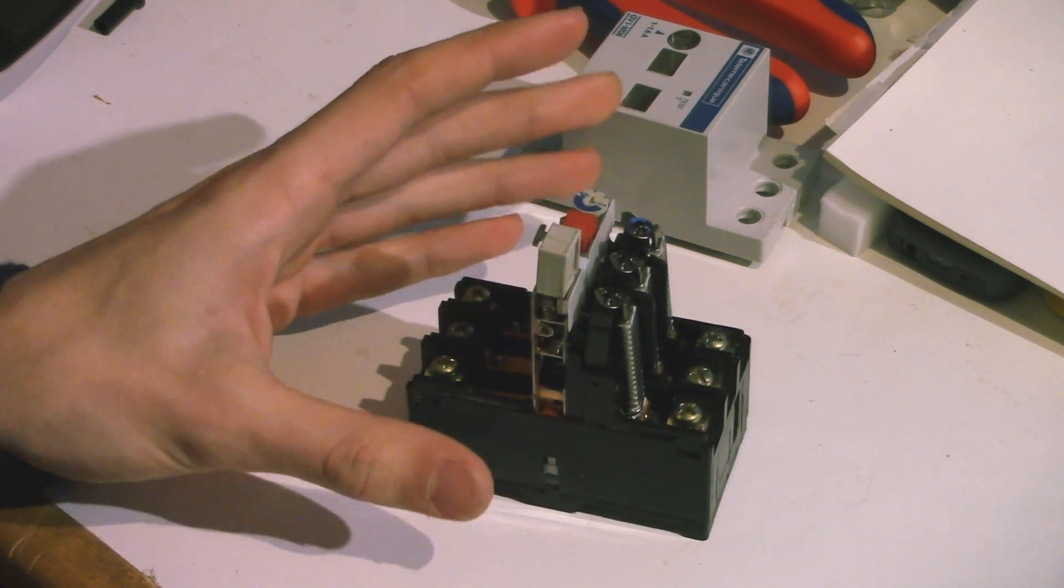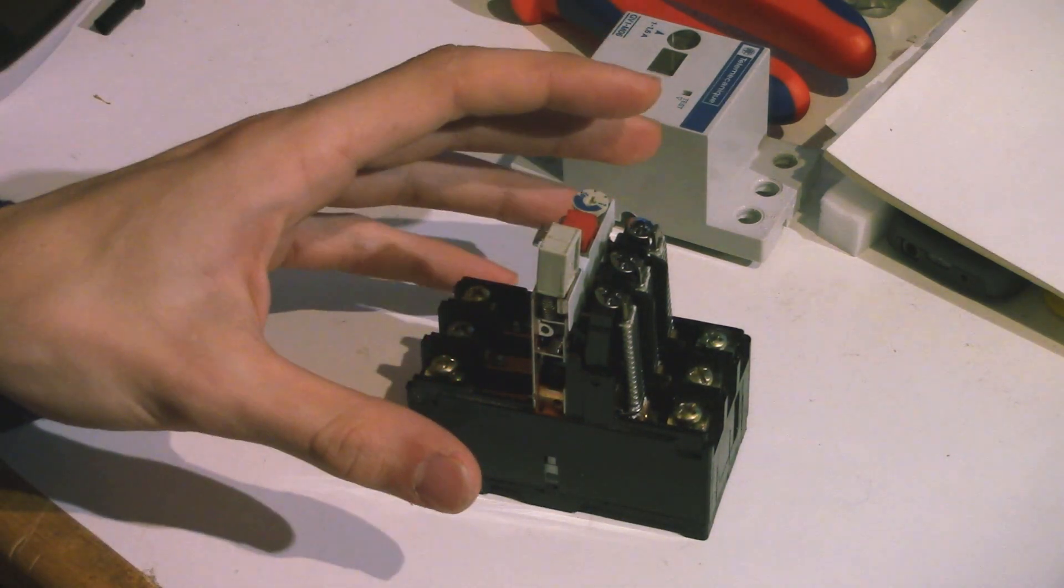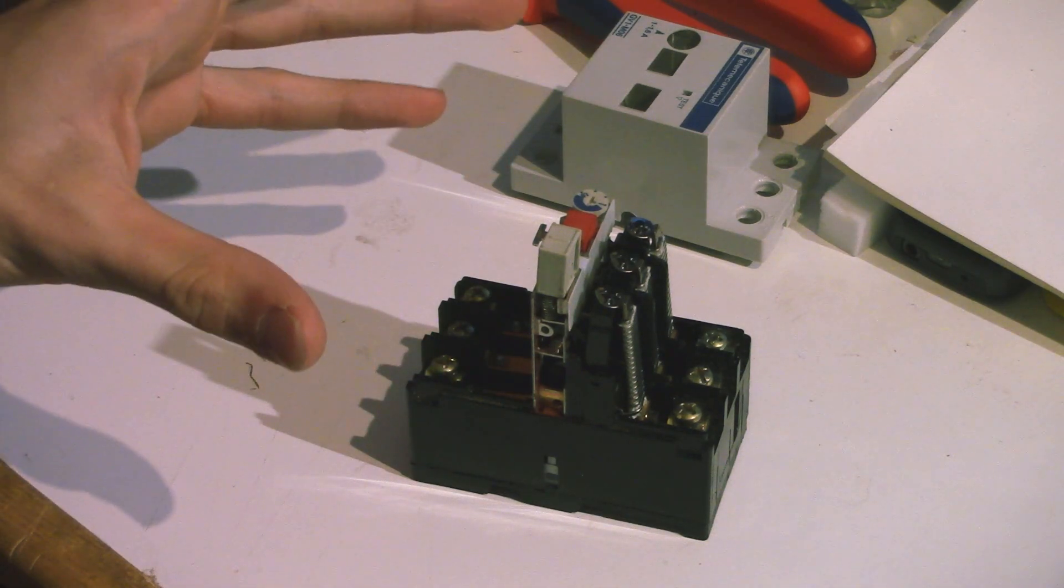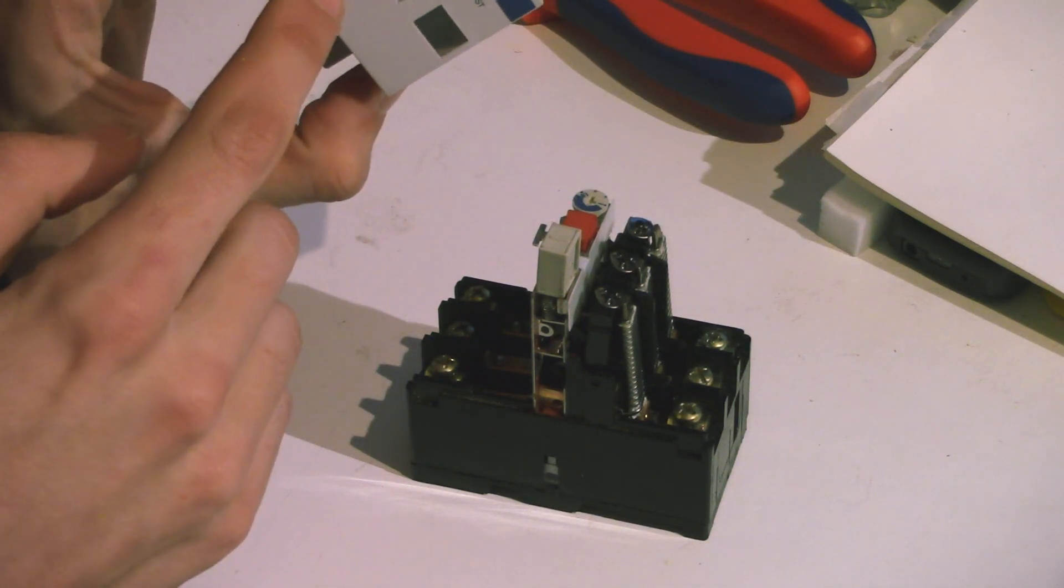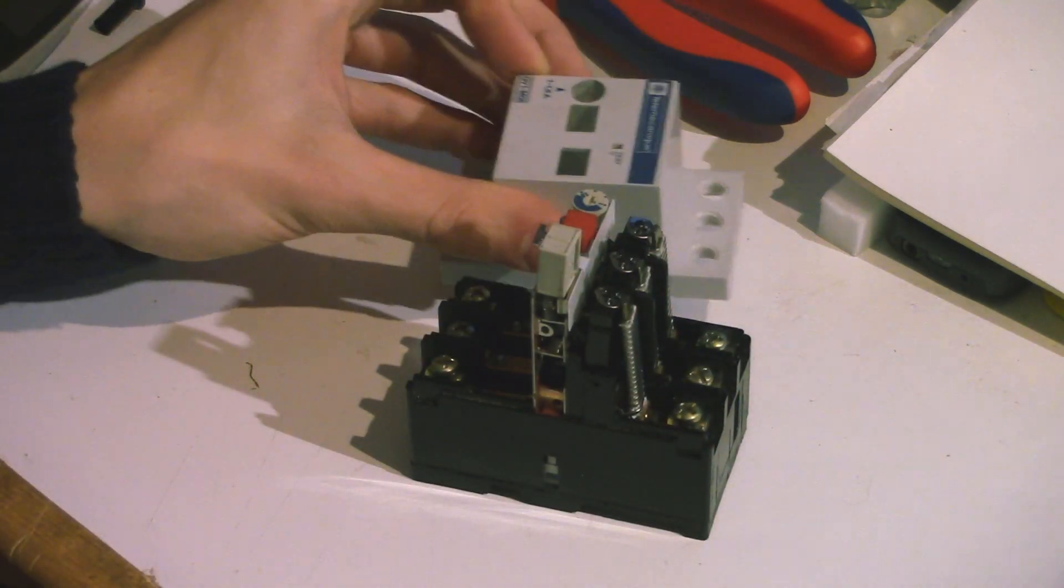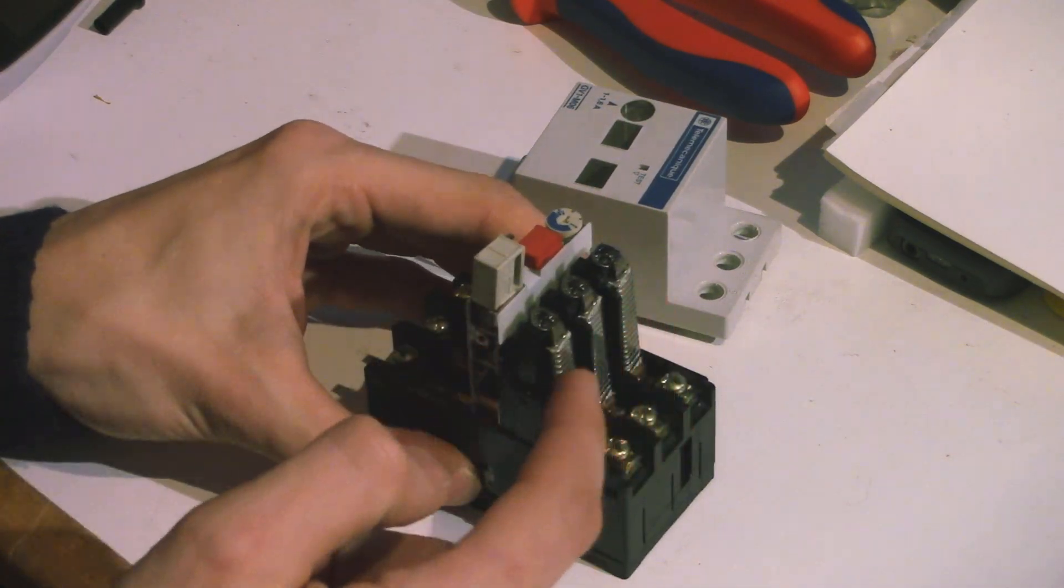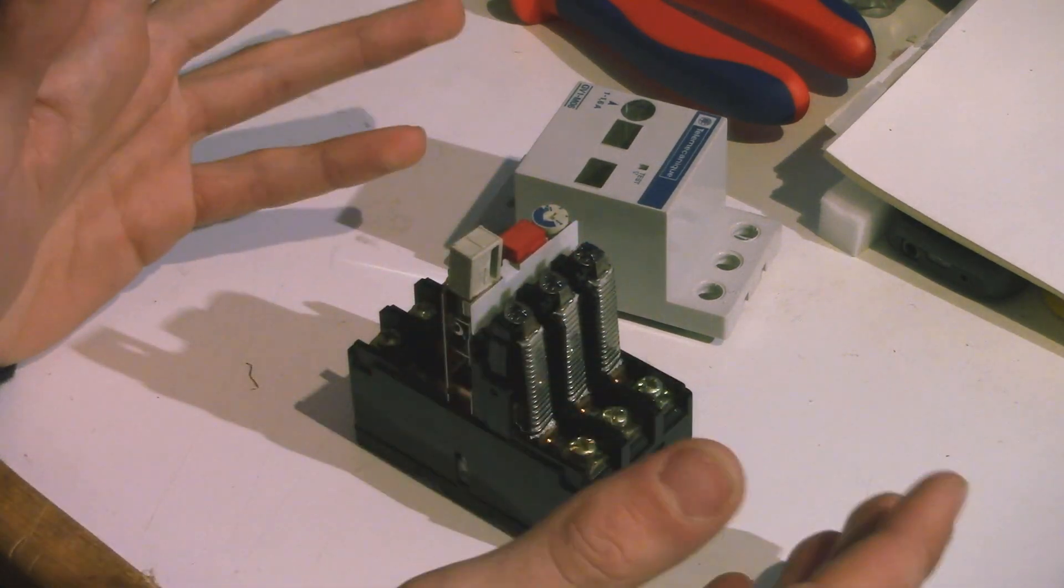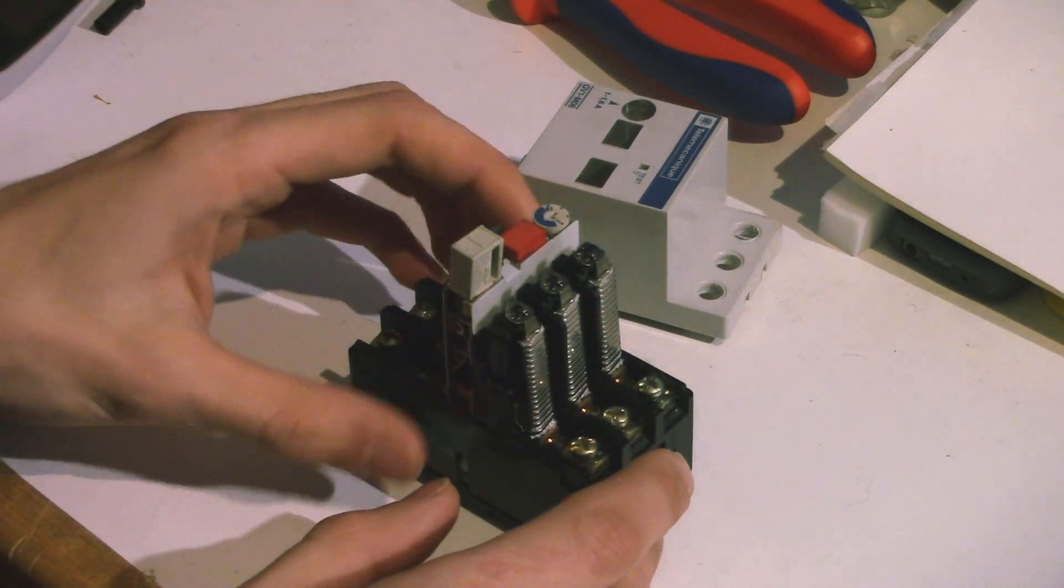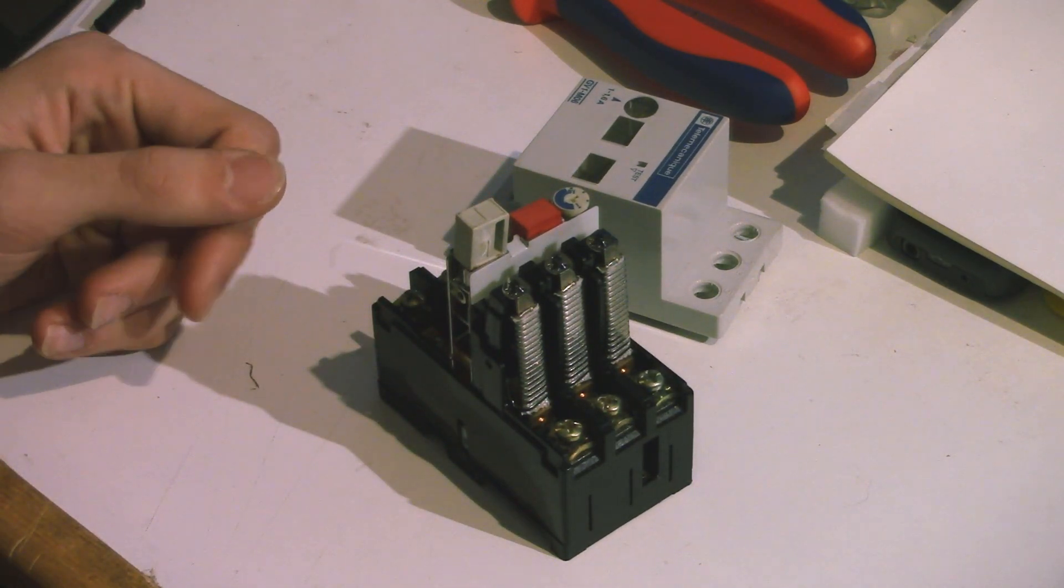So what happens when lots of electric current flows through this thing is these bimetallic strips start heating up and they start bending and they start pushing against this part of the mechanism, which then unlatches the spring. Now that takes a little while to happen. It might take a few seconds to happen. So it's not a very fast form of protection, but it is able to detect relatively low electric currents. So this one is rated for 1.6 amps, and this is able to detect anything slightly over 1.6 amps.